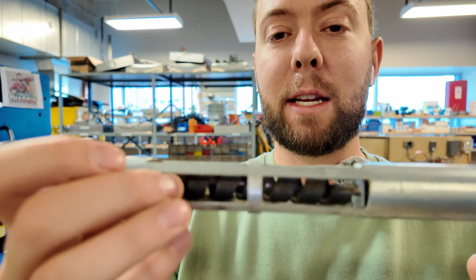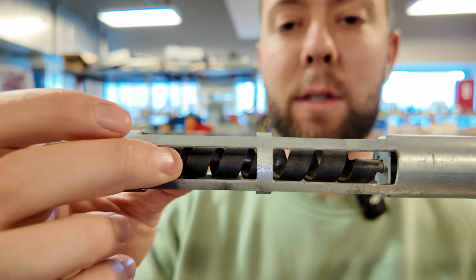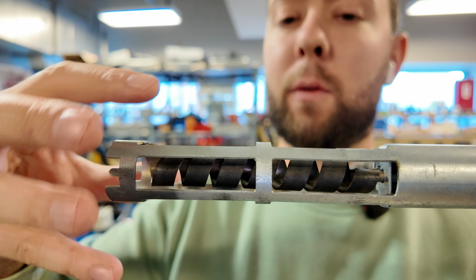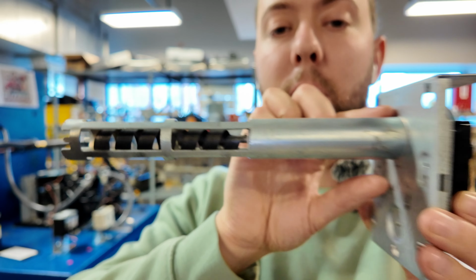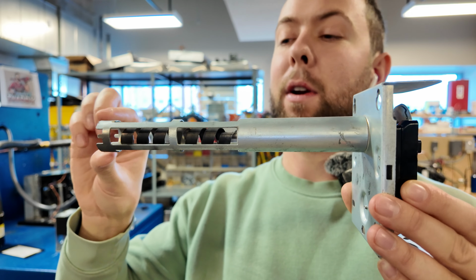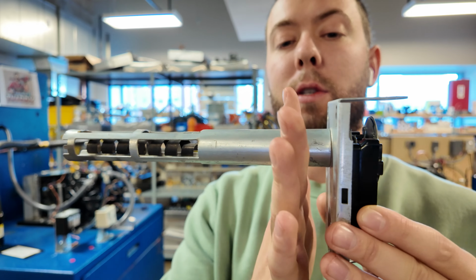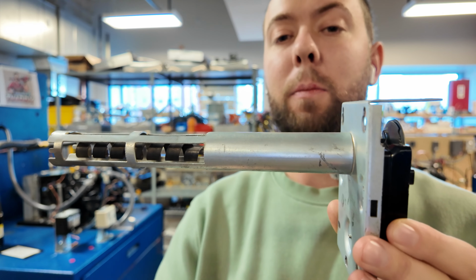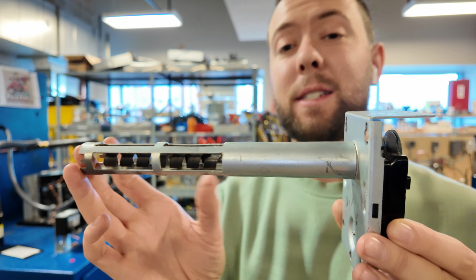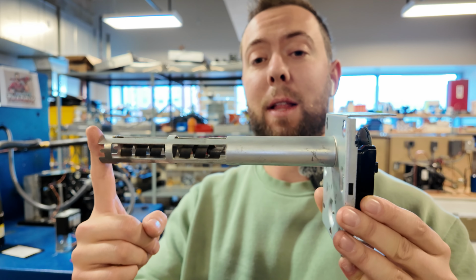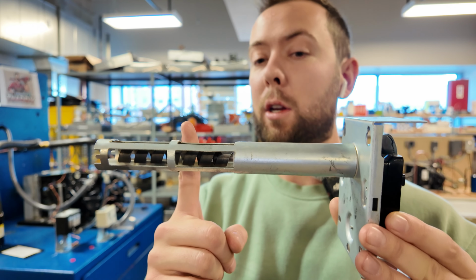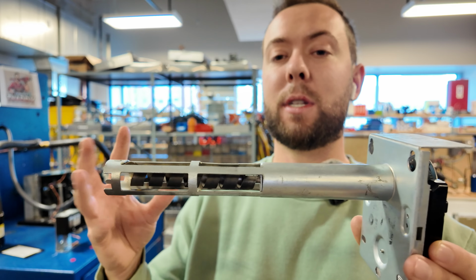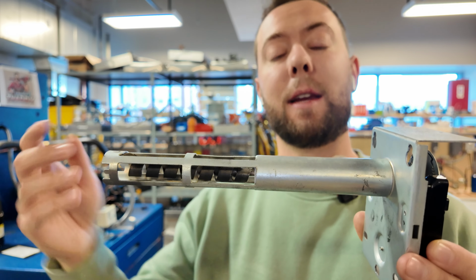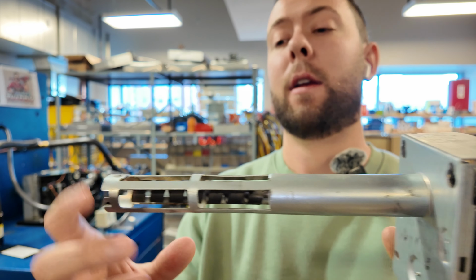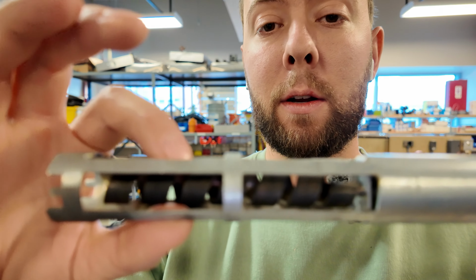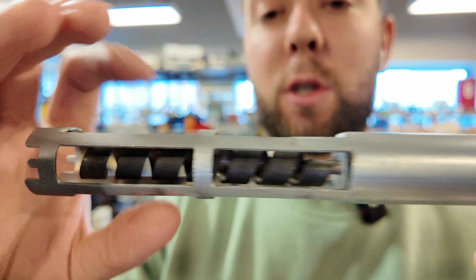And this actually, as it heats up, has two dissimilar metals, and it's going to spin when it heats up. This part is going to be mounted very close to your heat exchanger. So it's going to be screwed in, and this half is going to be inserted by your heat exchanger. If you ever replace these, you need to make sure it's the exact same length, because if it's shorter, you might not be reading temperature in the optimal designed area. If it's longer, the same thing. So that's very important.